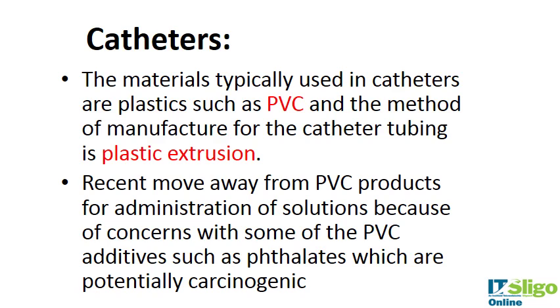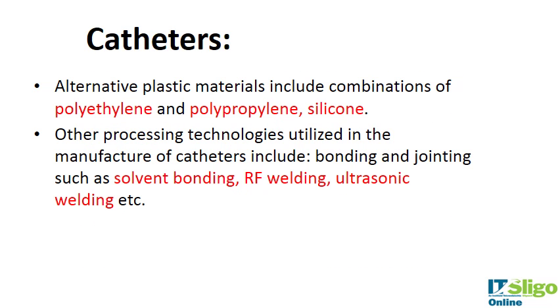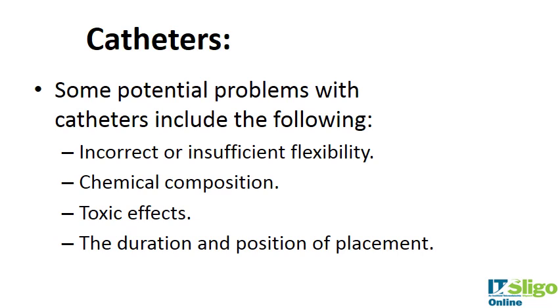The materials used for venous access devices, dialysis tubing, and enteral tubing are much the same — usually PVC, polyethylene, or polypropylene. How they're made is typically by plastic extrusion. There is currently a move away from PVC products due to concerns about additives such as phthalates. Alternative materials include combinations of polyethylene, polypropylene, and silicone. Other processing technologies besides extrusion include solvent bonding, radio frequency welding, and ultrasonic welding, which will be covered later in the course.